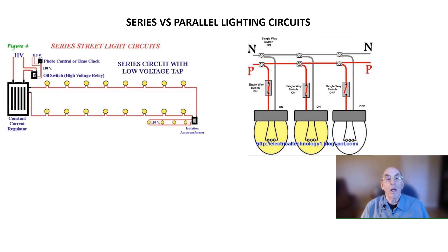the output voltage from the transformer must be 50 volts multiplied by the number of lamps in the series string. In my neighborhood, we had about 100 streetlights in a series string, so the transformer output voltage for this string of lights runs at about 5,000 volts.